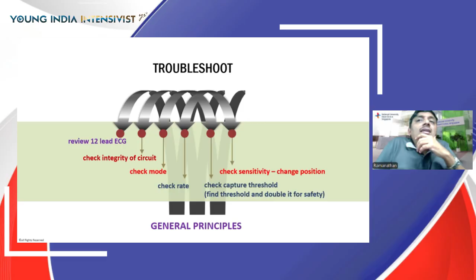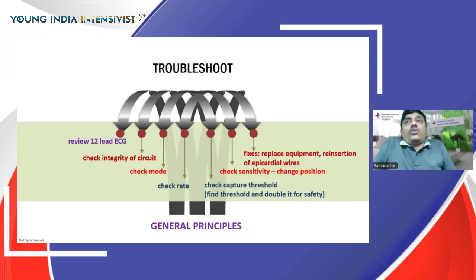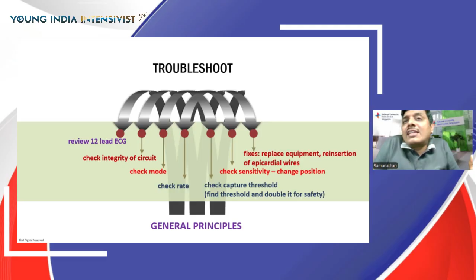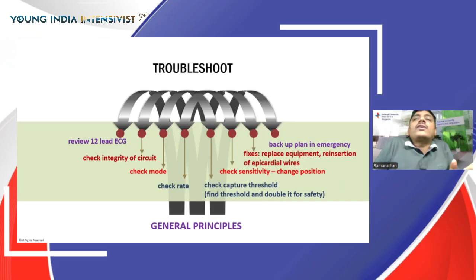You also check for sensitivity. Again, the same way as I told you earlier. Sometimes, if you just change the position of the patient, you may find that the pacemaker works perfectly well. Now, in addition to doing this, there are other fixes, such as, you may have to look at whether the equipment is worn off, whether the batteries need changing, whether there needs to be a reinsertion of epicardial wires or other wires. All these things will need to be evaluated. And while you are evaluating this, you may find that you may need a backup plan to meet some of the emergency situations. So what are the backup plans you make when you have a pacemaker troubling you?